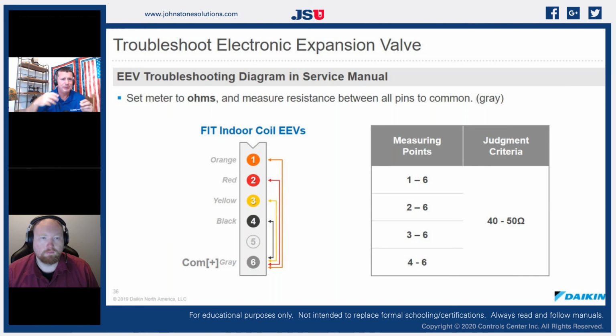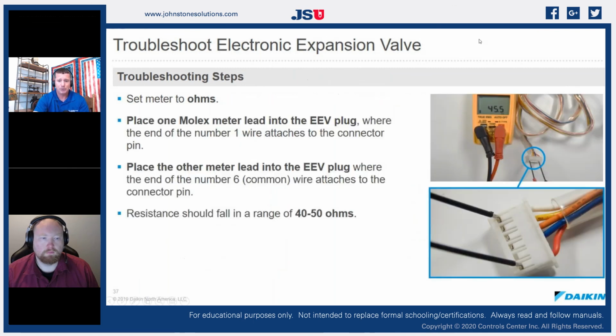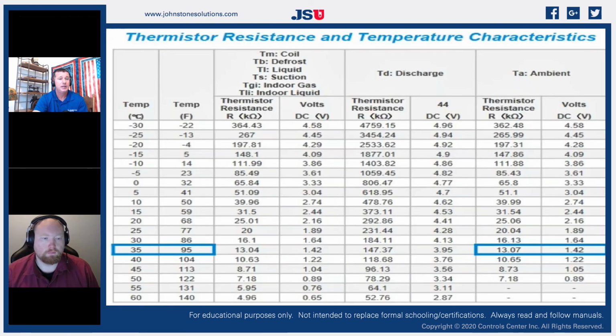And they're removable. You know, it's an external component. If we have a bad EEV, it's literally unsnap it, unplug it, plug in a new one. So a very simple operation. If we're looking at that, like I said, it's between 40 and 50 ohms. If we're looking at our temperature sensors and pressure transducers, we have a chart in our installation and service manuals that shows us exactly what those should be.